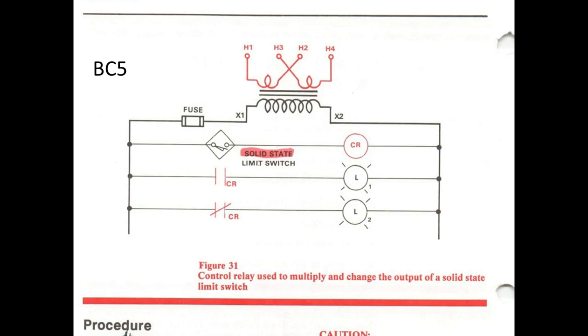So here they're saying the title is using a control relay. First of all, most of - probably 90% of - your solid state relays only have one contact. So this one's only got one contact. It simulates a normally open contact. At most I've seen some with a single pole double throw, which sounds like two contacts, but one is normally open and one is normally closed.